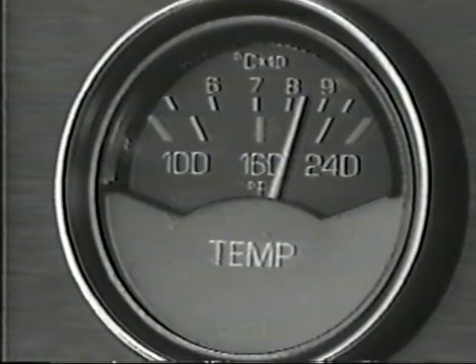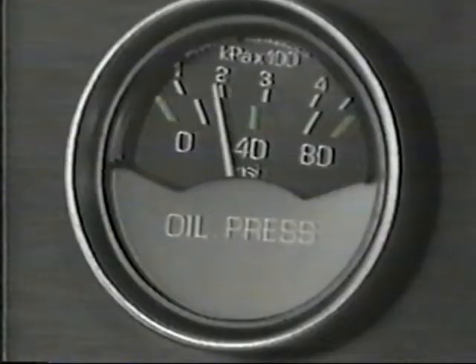During our discussion, we'll be using alarm stats, which are temperature sensors, and pressure stats, which are oil pressure sensors. The set point for an alarm stat is stamped or engraved on one of the hex flats. This one is set at 220 degrees Fahrenheit. The set point for a pressure stat is represented by the last two numbers of the part number. This one will alarm at 5 pounds. Since the many makes and models of engines have different operating characteristics, alarm stat and pressure stat set points are chosen according to a particular engine's maximum allowable operating temperature and its minimum allowable hot idle oil pressure.